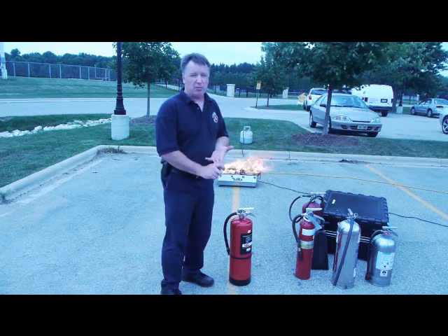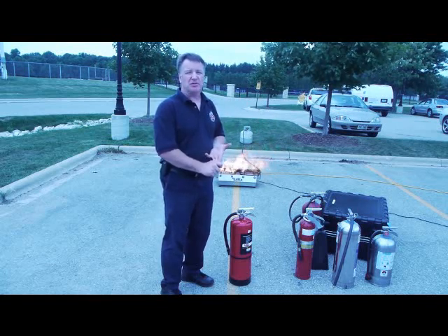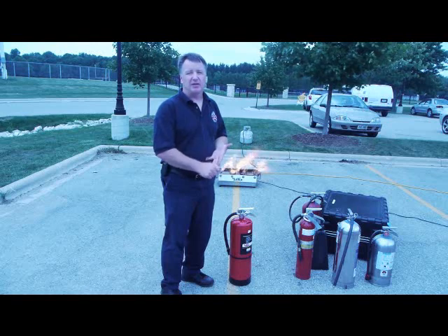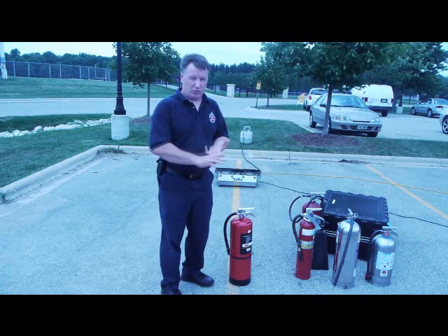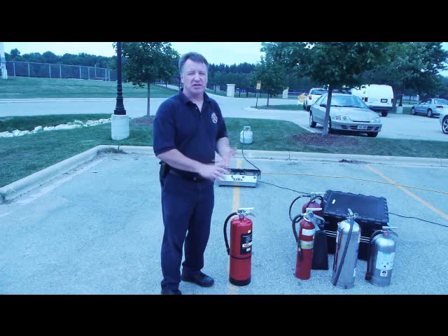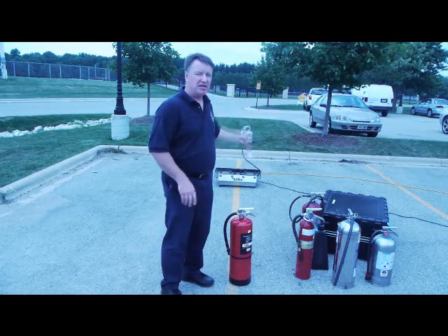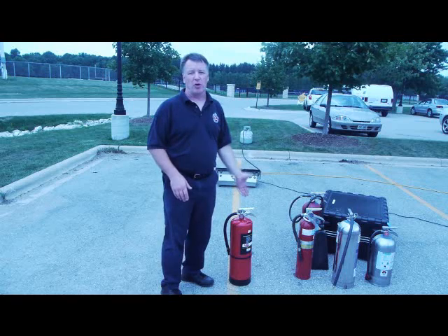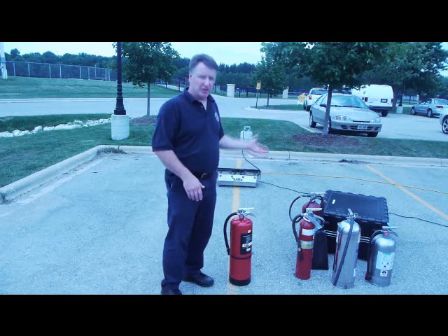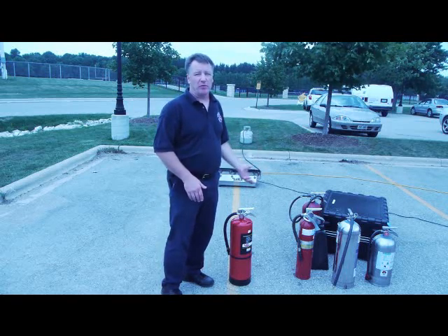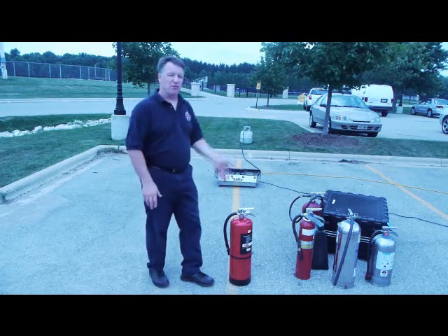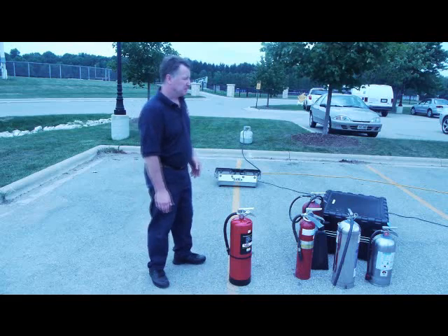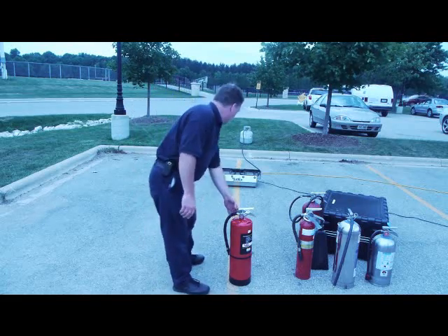Third is have someone call 911. Not all alarm systems are going to be tied into a fire department or a response center. So those have to happen before you decide to fight this fire. The fire needs to be small enough that you can put out with an extinguisher. If it's too big, you need to let it go and get yourself out and be safe. So keep that in mind. Those have to happen before we go into using the extinguisher. So let's see if we get our fire going again.